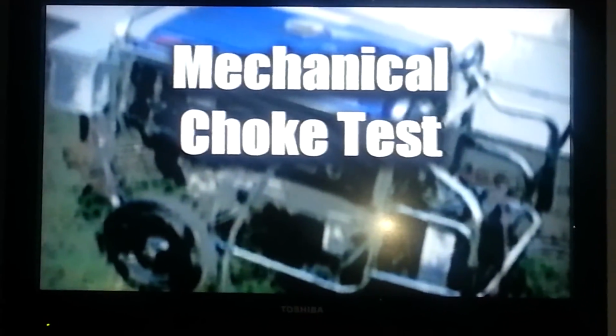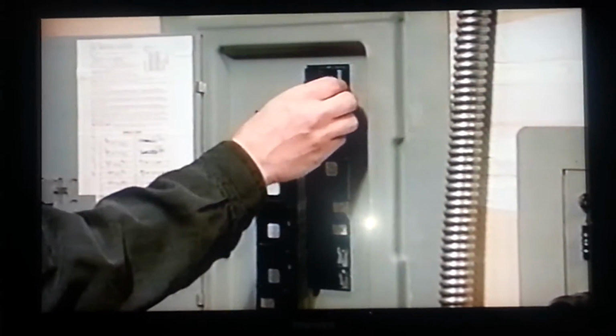If your generator has a mechanical choke, you will need to check its operation. To do this, slide switch 1 on the engine control circuit board to the on position using a pencil. The mechanical choke drive motor will be driven to one extreme of its travel. Slide switch 1 to the off position, and the mechanical choke drive motor will move to the other extreme of its travel. To test the system, first reinstall your load center cover and turn on the main breaker to restore power. Remember, an electrical inspection may be necessary at this stage.